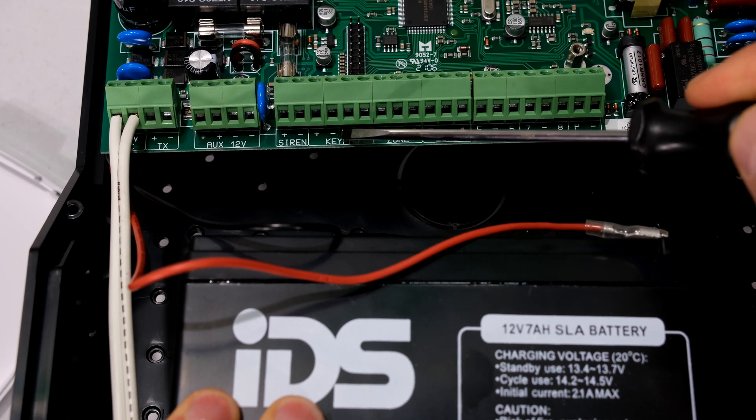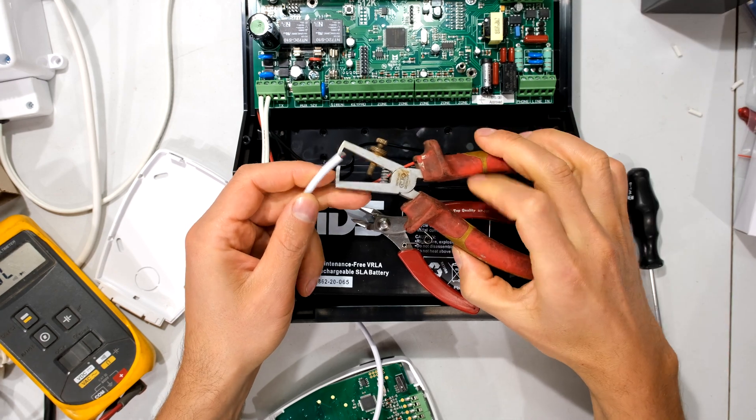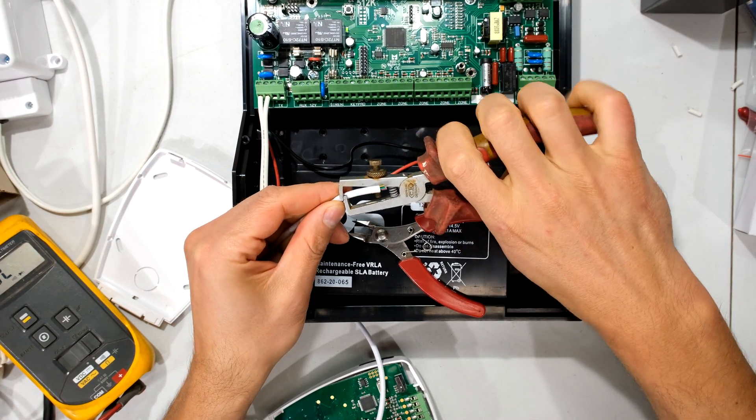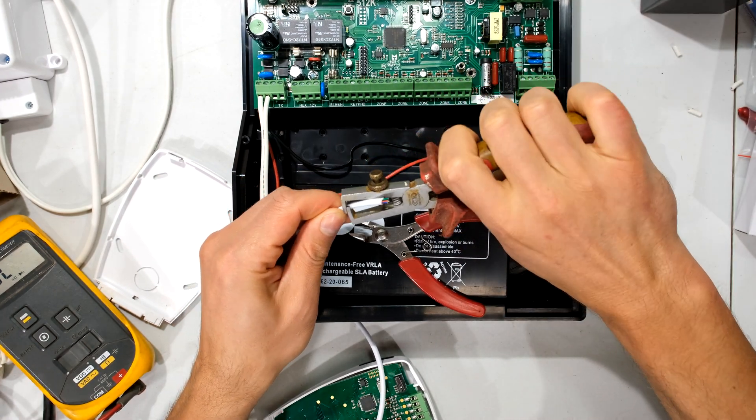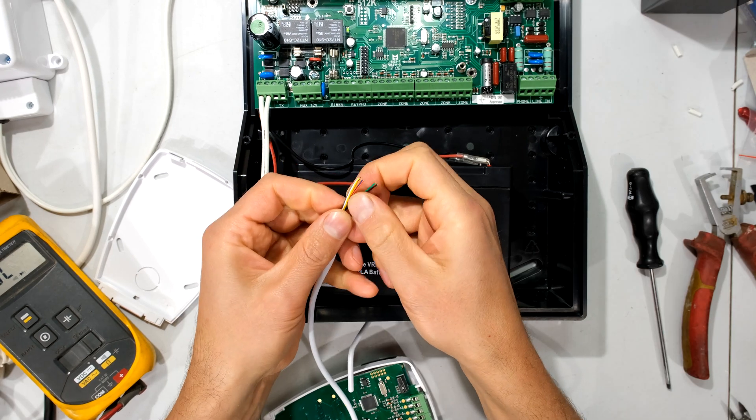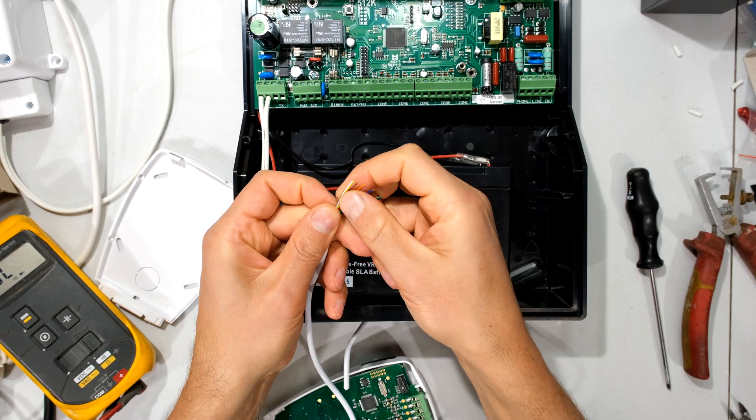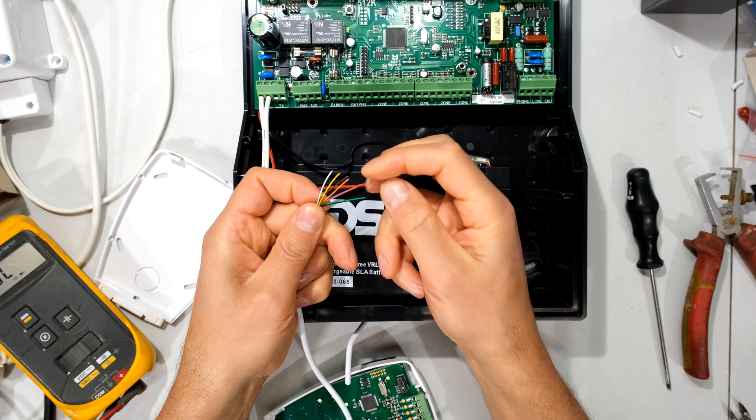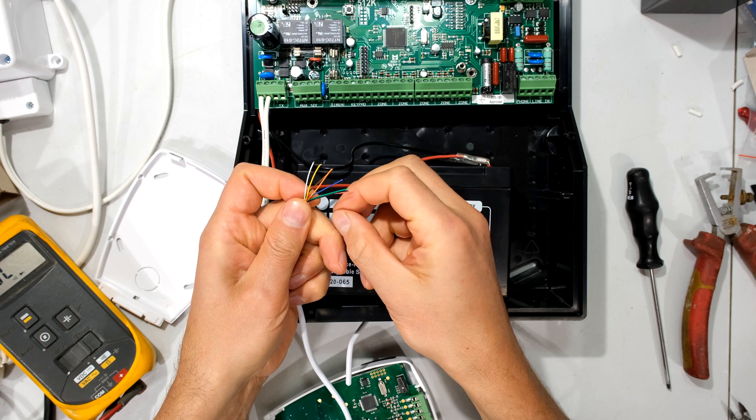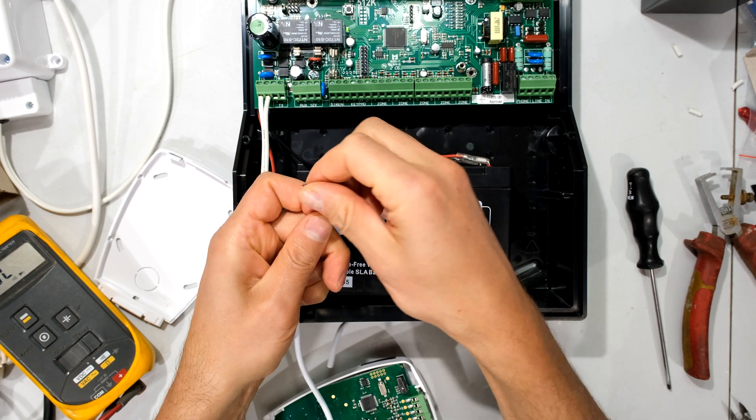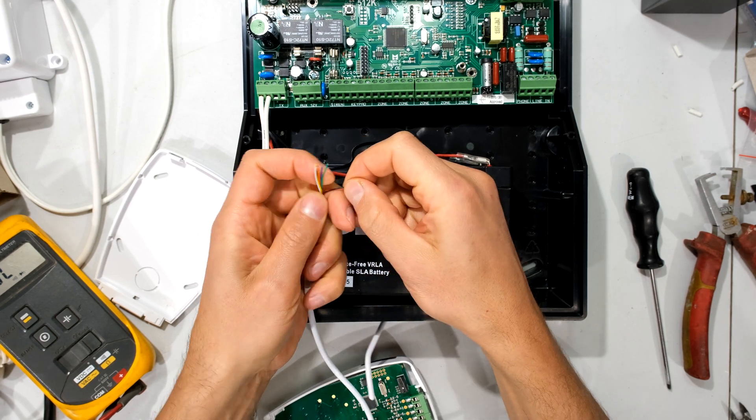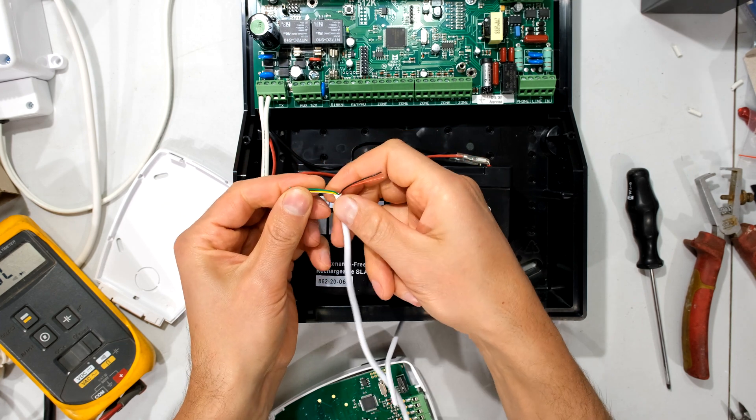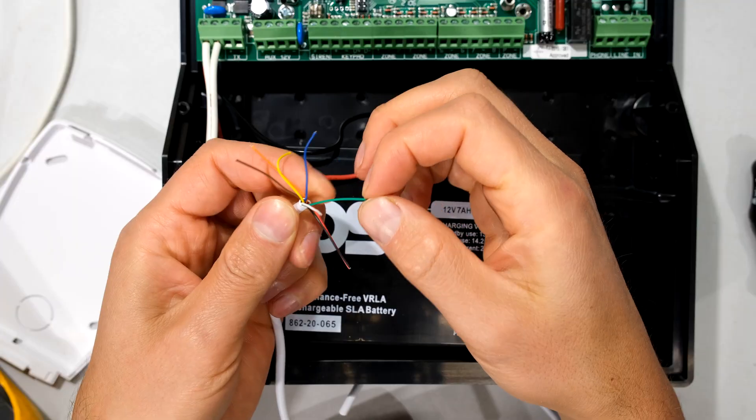I will show you how to connect the keypad now. You can use wire strippers, and I'm just going to remove a little bit of the jacket here. Now for the keypad, you only need four cores. So I'm going to now separate these. I only need the red for positive, the black for negative, and I just need two more for the data plus and the data minus for that bus.